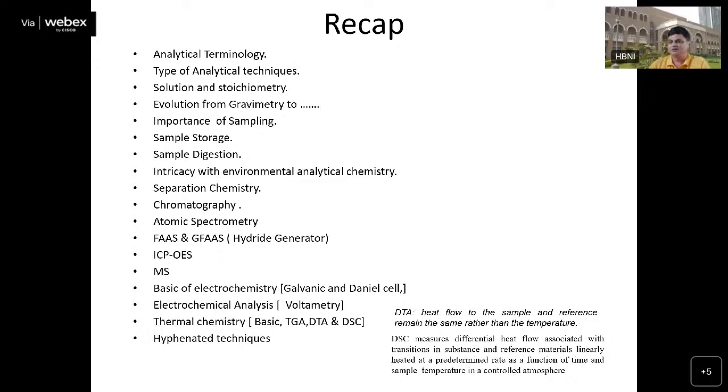Basically here in ICP-OES we can use the emission lines both from the atoms as well as from the ions. So that's a distinct advantage because they have temperature, because we are using a plasma. And here our analytical zone is about, say, in the range of 5,000 to 6,000 Kelvin. So at those particular temperatures, there are many elements we are able to detect.